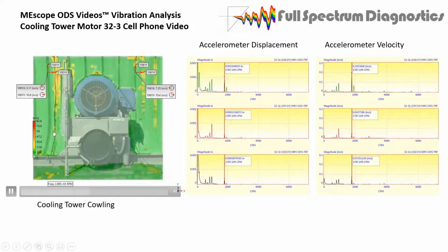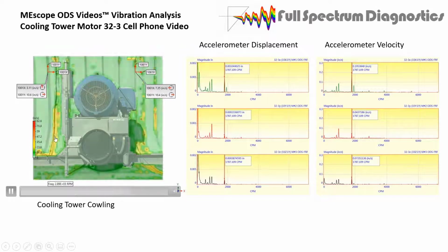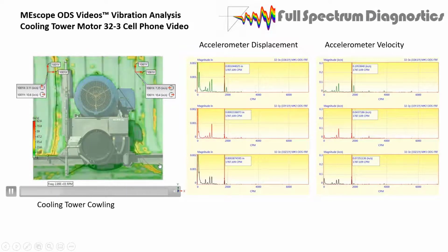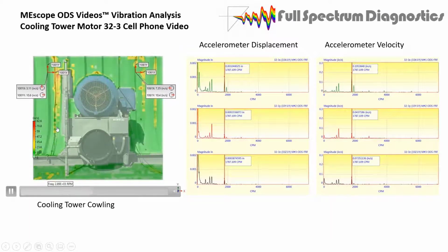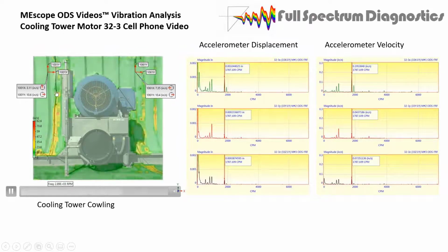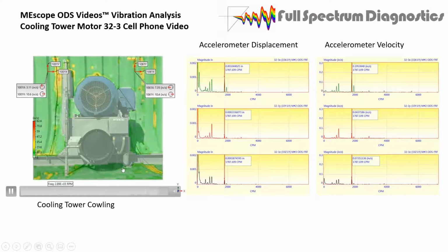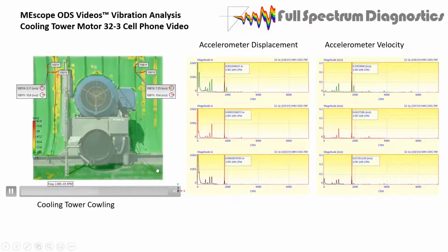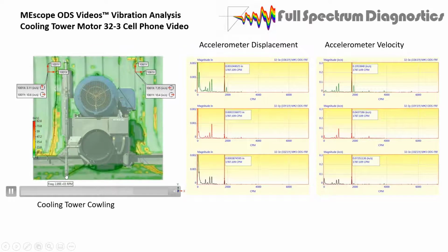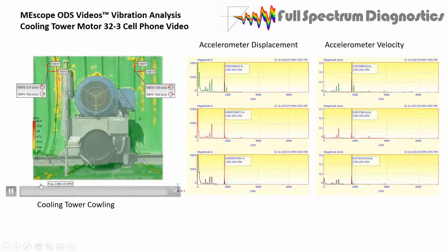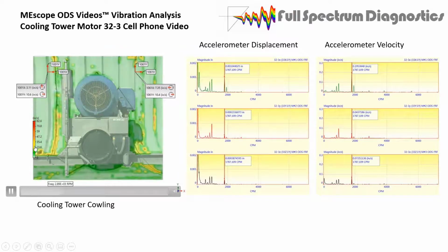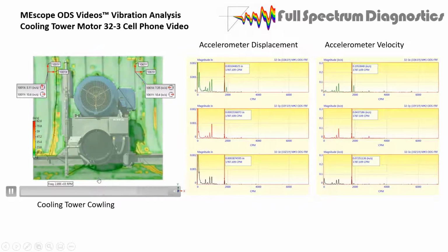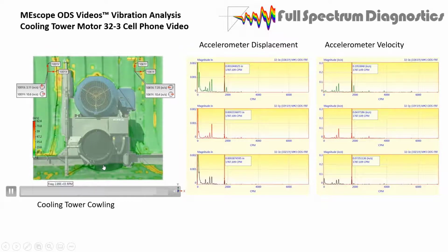There's also a cable running down here that is, I'm not sure what it is, for lightning strikes or whatever, a grounding cable. There's a cable for my transducer running across the floor, and that's swinging a little bit, so you get much higher vibration from a swinging rope or a chain or what have you. This is interesting. This is where the floor vibration is. Over here, you can see it from the accelerometer cables, but on this side, all you're seeing is a crack in the floor, and you can see the change in vibration there. And we're in big, really big numbers. So just to give you an idea of how different the background can be compared to the actual vibration of the machine.